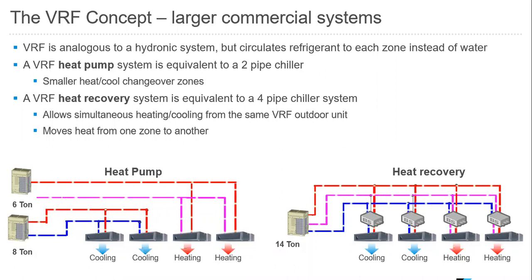By contrast, on the right-hand side, bottom of the screen, I have a 14-ton outdoor unit, and that outdoor unit is a heat recovery system. So it's a different model number than the heat pump outdoor units. This heat recovery outdoor unit has a special device we call a BS box downstream, and that BS box allows us to have simultaneous heating and cooling. The way that happens is that we're able to provide, through the BS box, hot gas for heating or subcooled liquid for cooling. On a day when we have heating and cooling occurring at different times during the day and in different parts of the building, we can take all of the energy that goes into heating and put that into cooling energy for the system. This is called a heat recovery system.